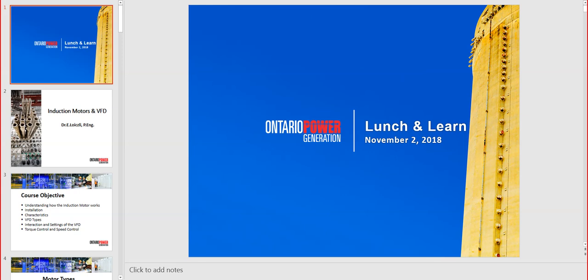All right, so the topic today is variable frequency drives. The reason I'm doing this webinar is because around the plant we have many applications with the VFDs, and definitely some of them are not completely understood, or the VFD is not properly set up, or altogether the finding is that the VFD is not really the box that is used, and instead of the VFD we have another box that is, for instance, a soft starter. Please do not hesitate to put questions and interrupt me whenever you want.